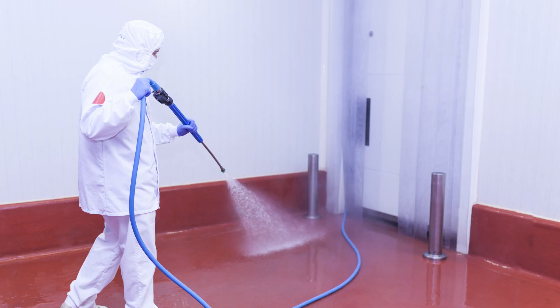There's no other way. On the other hand, there are applications where the environment is very wet, with a lot of moisture, or very dusty, or even in explosive areas. There it's clear that the busbar system is impossible to use, because it has open layers and the risk is very high for short circuits, and in the end there's a risk of death, very dangerous. So in normal countries this system must not be used in such applications.